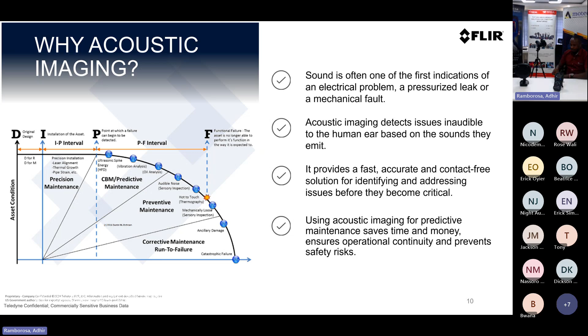So why acoustic imaging again? It addresses multiple markets and customer needs. Part of it will be electrical faults, which is a major one. We'll cover partial discharge testing, corona, and mechanical applications like rotating equipment, where you can do your inspection and discover faults in rotating equipment, belts, bearings, and conveyors. And also gas leaks: compressed air, which is major in manufacturing and processing industries, steam systems, and natural gas. I think those are the major markets acoustic imaging addresses, because we take the best of.